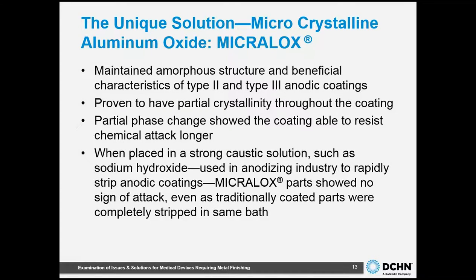So it's pretty impressive, right? So what you just saw is a new patented technology that we call MICRALOX. It is the new standard of anodic coating for reusable medical devices. Through XRD analysis, we were able to prove the existence of partial crystallinity throughout the coating, thereby significantly increasing the resistance to chemical dissolution, but still maintaining the most beneficial aspects of traditional anodize. This partial phase change did the job. When subjected to high and low pH chemistry, there's a very significant difference in performance over both type 2 and type 3 conventional coatings.